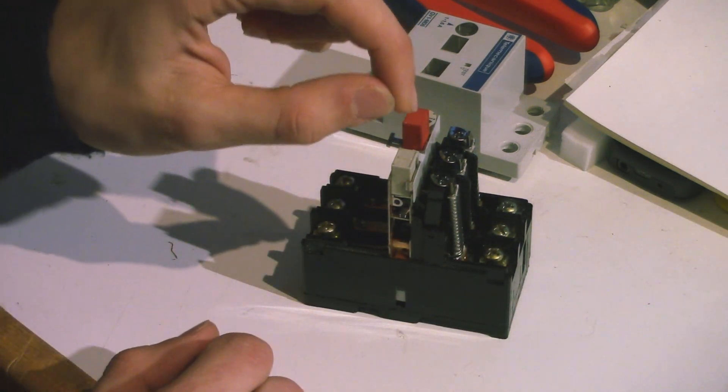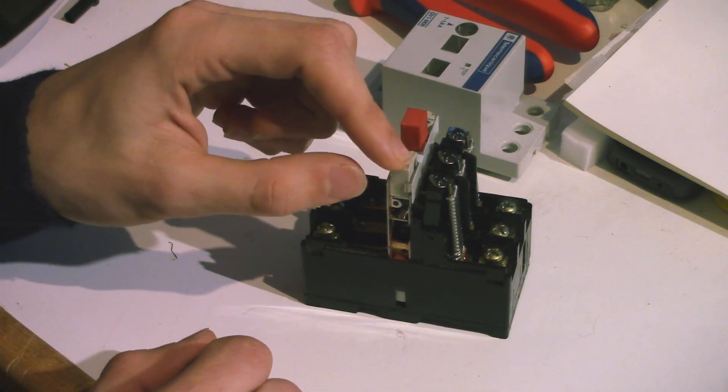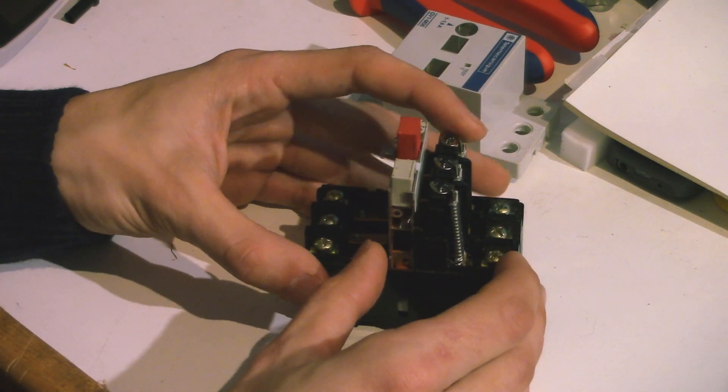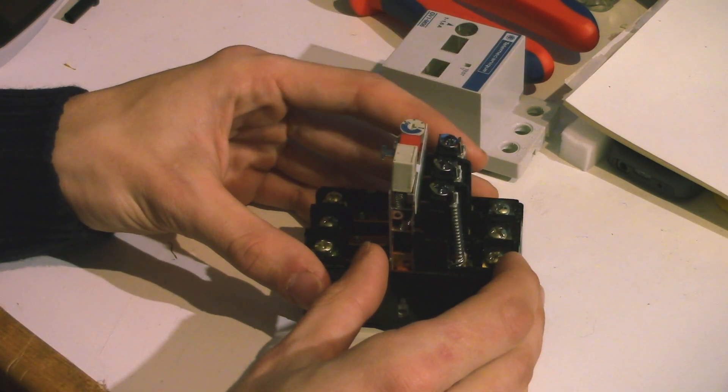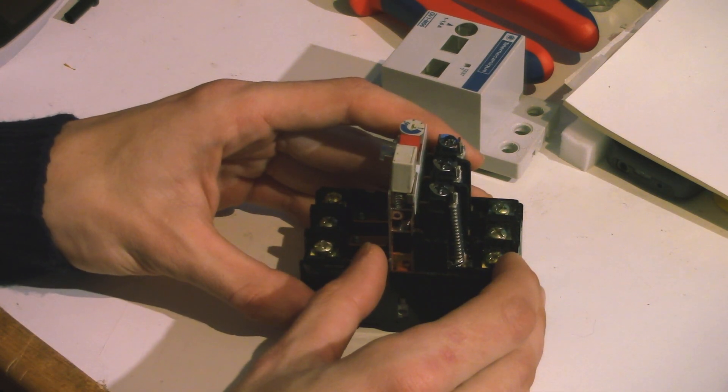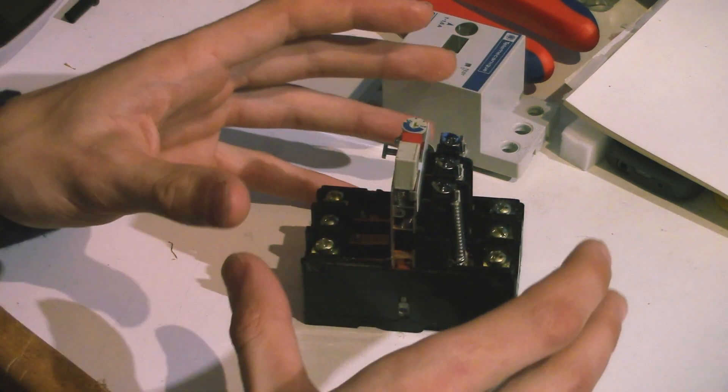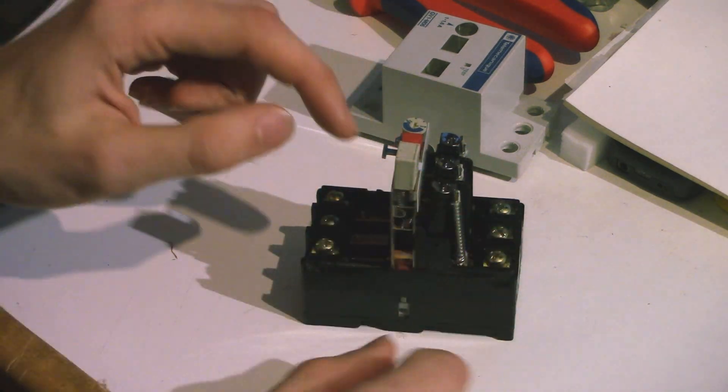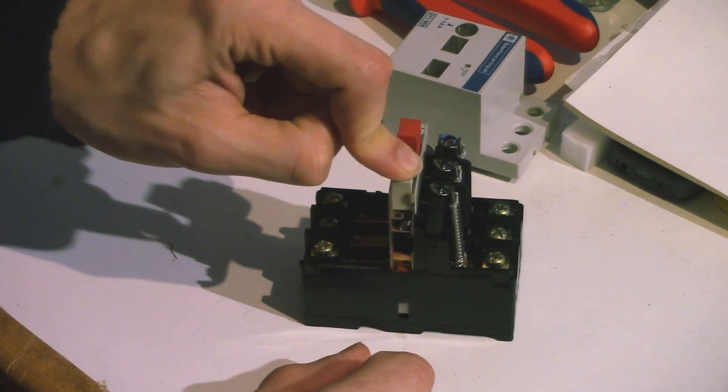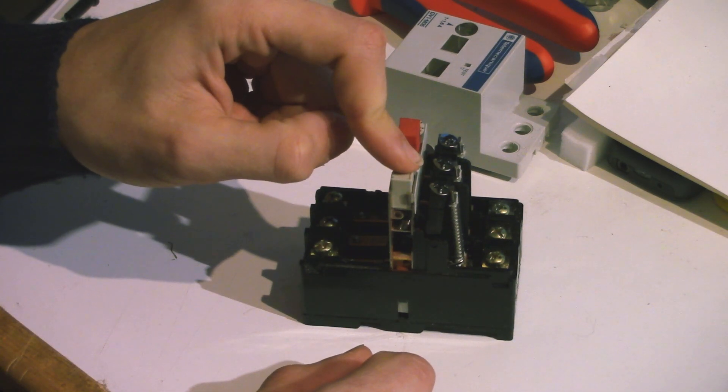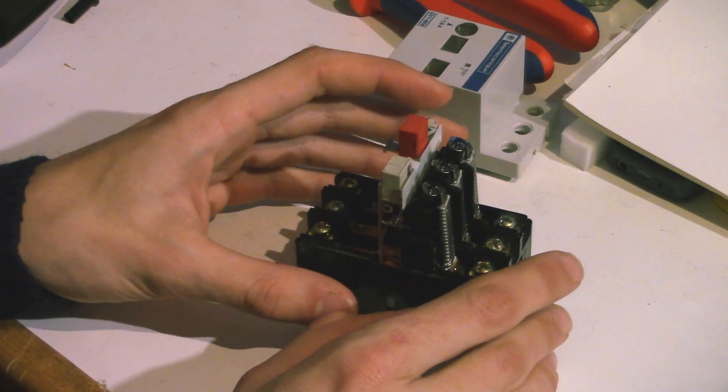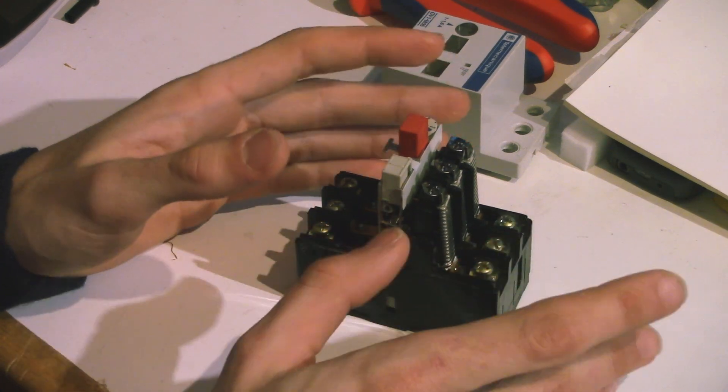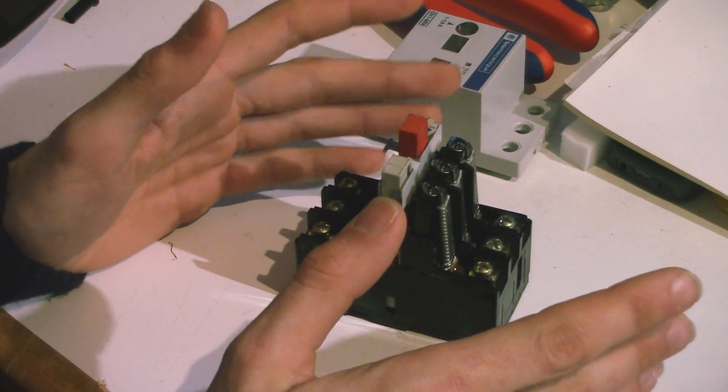So when you turn it on, you load a spring and lock it into position. And when the breaker opens, that switch is simply unlatched and it jumps back into the open position. So the energy that is required to actually open the switch is already put in by the person who switched it on. So now, of course, the question is, what causes this spring mechanism to be unlatched and this switch to jump back open?